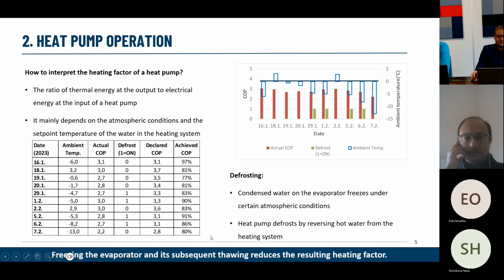But you can see that there's a big variance versus the data sheet. And ironically, it was at -13 ambient, so the already unfavorable condition, where the actual COP was 2.2, it should have been 2.8 according to the data sheet. So you can see that, you know, it's good to understand how the heat pump actually behaves in real case scenario. The variance might be also because of the variation on the actual water temperature that's circulated in the heating system. If you set the heating temperature up in terms of the water, it decreases the performance.